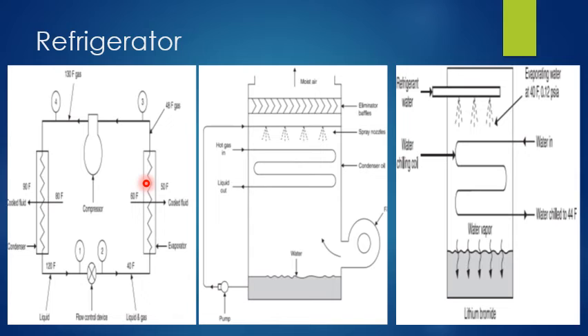Process 1 to 2: at point 1, the refrigerant is in the liquid state at relatively high pressure and high temperature. It flows to point 2 through a restriction called a flow control device or expansion device, losing pressure going through the restriction. The pressure at 2 is so low that a small portion of the refrigerant flashes into a gas. But in order to vaporize, it must gain heat, which it takes from the portion of the refrigerant that did not vaporize, thus cooling the mixture and resulting in low temperature at point 2.